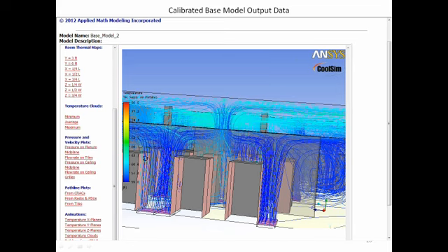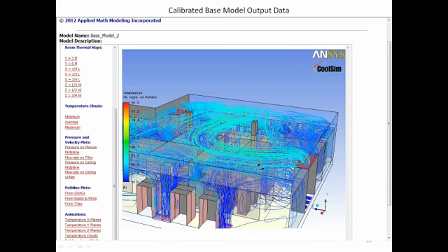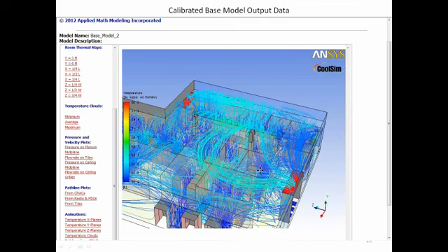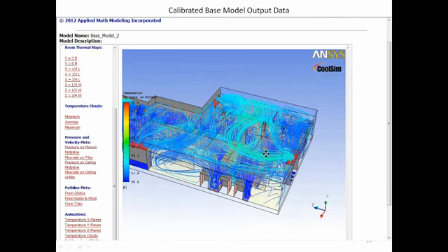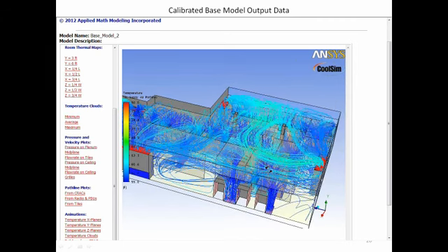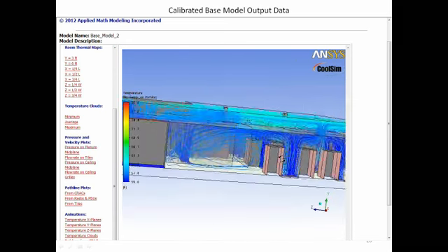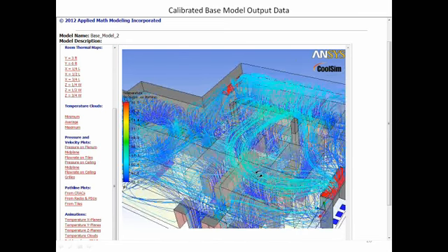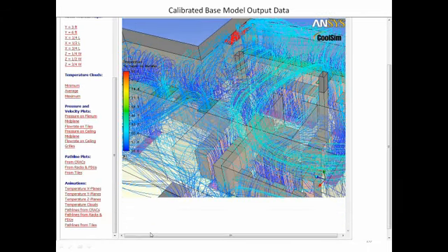So this is going back at a temperature of 58, 60 degrees, which means the delta Ts are very poor in the CRAC, and the whole thing is terrible. This is also a good illustration to show a customer, if you're a colo provider, that the room is just way too cold, because customers will often push you to run them more inefficiently than you'd like, because they want to make sure their equipment is, quote, safe.